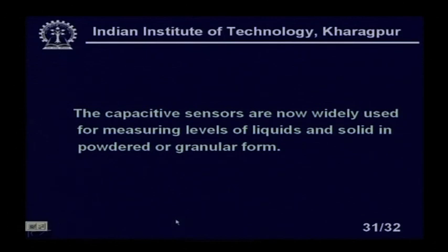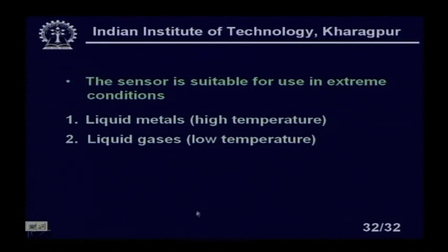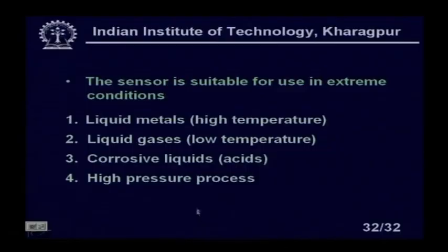Capacitive sensors are widely used for measuring levels of liquids and solids in powder or granular form. They are suitable for extreme conditions: liquid metals at high temperatures, low temperature gases, and corrosive liquids like acids and caustics where other sensors fail. For a stainless steel container with corrosive liquid, capacitive sensors work well. They also work in high pressure processes where other sensors fail, as they are totally independent of the pressure of the liquid.